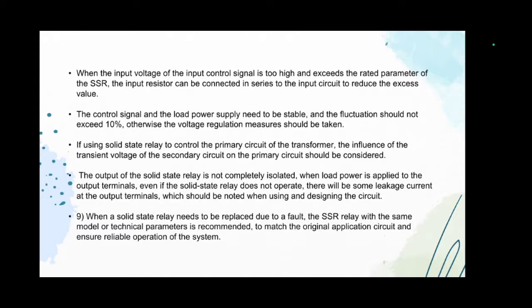So, take note, and be reminded of the voltage regulation measures. 7. If using a solid-state relay to control the primary circuit of the transformer, the influence of the transient voltage of the secondary circuit on the primary circuit should be considered. So, the primary circuit should be considered since the transformer may also generate surge currents.